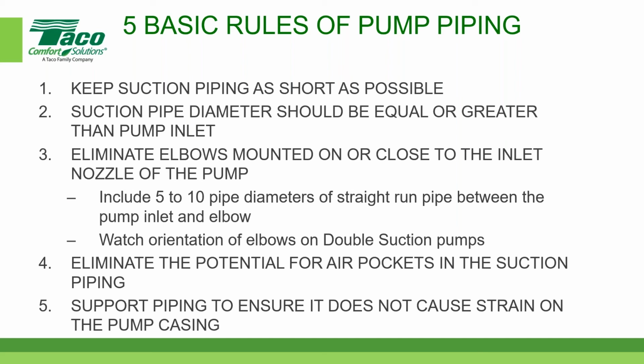And then on these double suction pumps, you've got to watch the orientation of the elbows. And I'll show you what I'm talking about very shortly. But you need equal flow to get on both sides of that impeller, top and bottom. If it doesn't do that, you're going to wear things out or cause other issues very, very quickly.